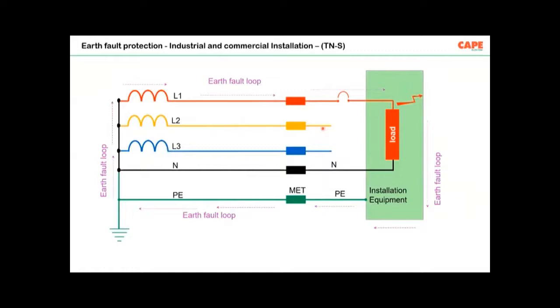The impedance of the circuit ensures whether the protective device is able to trip or not. So basically, earthing is all about making this impedance as low as possible. Installation or equipment earthing means the impedance of the conductor must be very small. That means no loose contact, sizes must be higher, and so on.